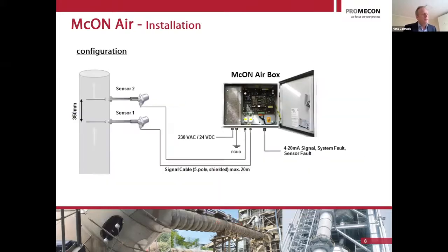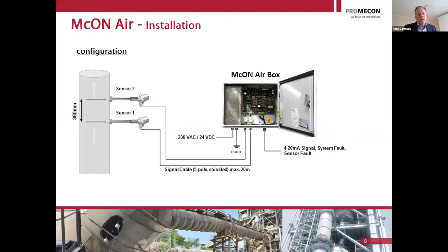This measurement has very big advantages over any other approach for measuring gas flow in hot gases. The main advantage is that the measurement is either physically present and accurate, or it fails — there is no in-between drift. If you clean the sensor and put it back in, you will have exactly the same reading as before. Our company has been working on this measurement for over 20 years to make it the most stable measurement in the industry for dusty flows. We have many applications with no failures over many years, so the operator in the control room will have an accurate reading at all times.